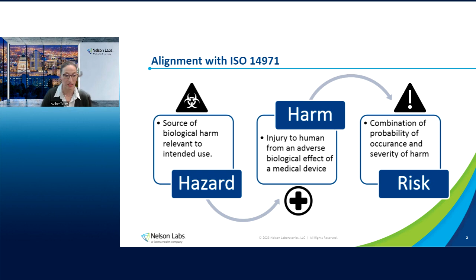I pulled this figure from ISO 14971 because it helps me think about hazard, harm, and risk. I think it's really important, especially for me because my role is a risk assessor, that I wrap my head around these terms so I'm very clear in my documentation. So this is from figure C1 in the 14971 standard, where when we talk about hazard to harm, there is some consideration about a hazardous situation. And this again is where we talk about intended use, foreseeable misuse, bioaccumulation.